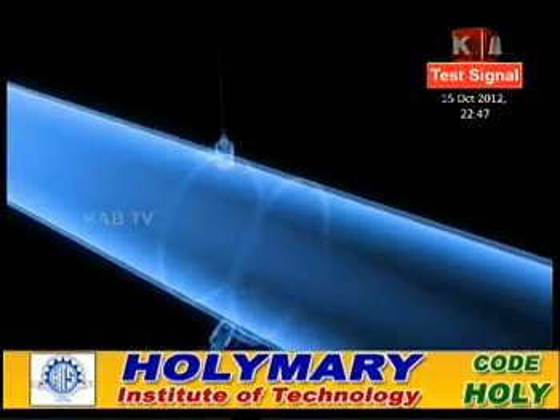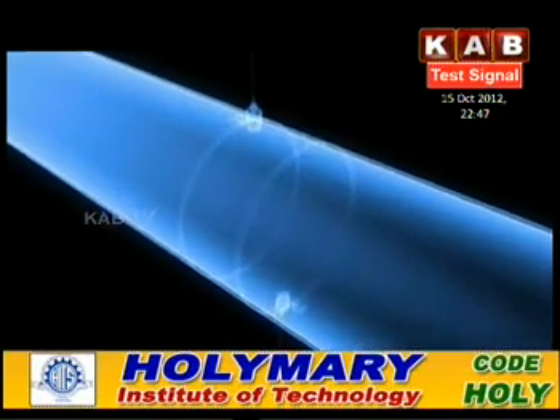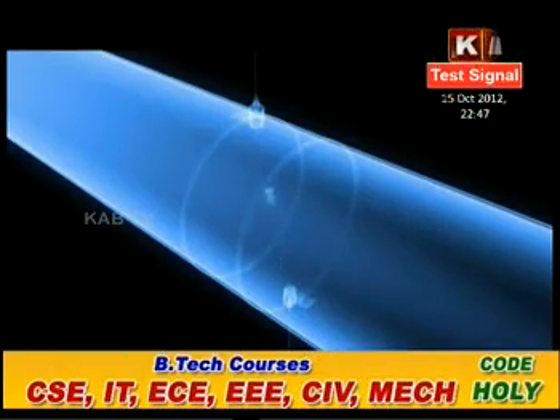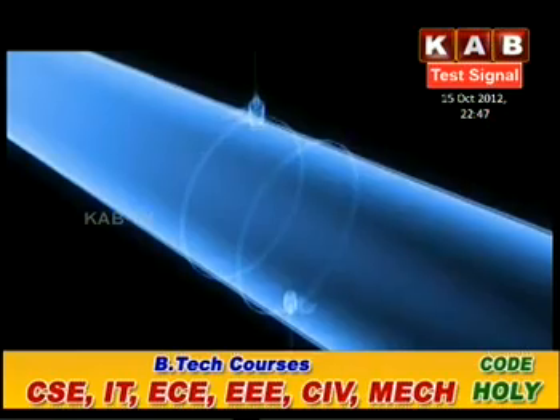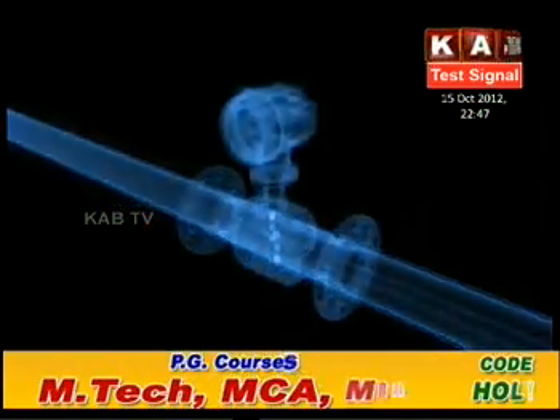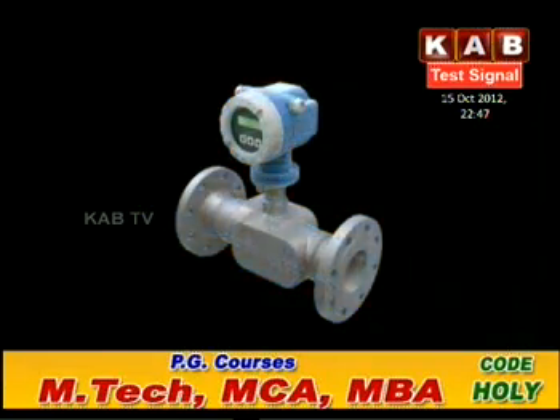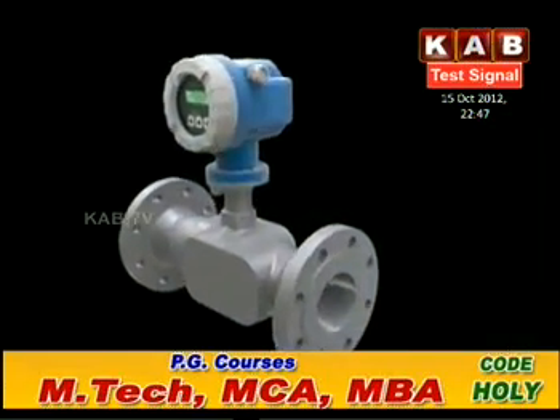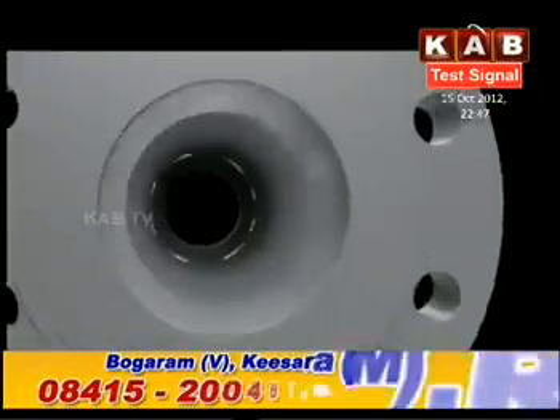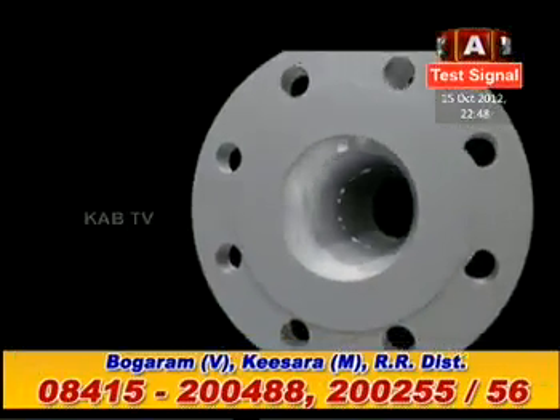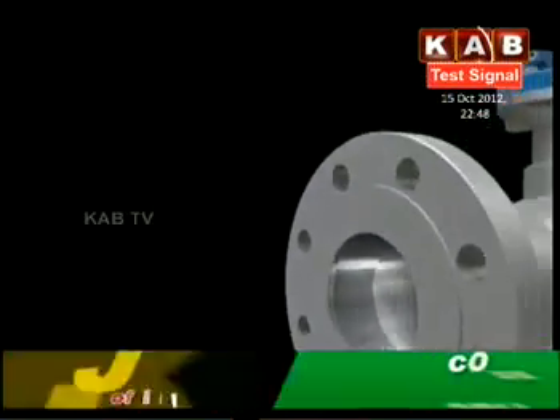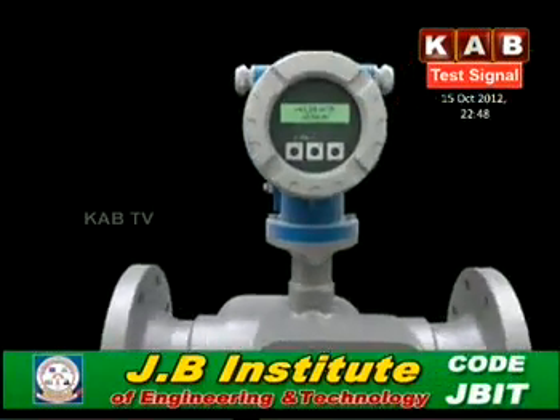The clamp-on design is unique because flow rates can be measured in very large pipes, up to 4 meters in diameter. This possibility increases the areas of application, for example in the water and hydroelectric industries. Flexible mounting, process safety, and cost-effectiveness are the distinctive advantages of ultrasonic flow measurement.